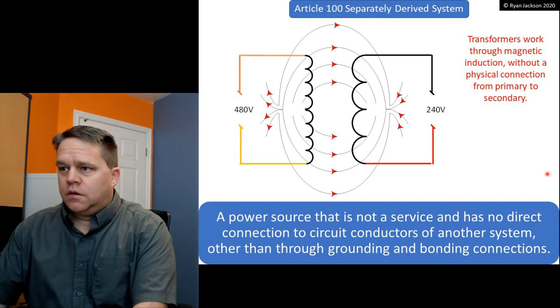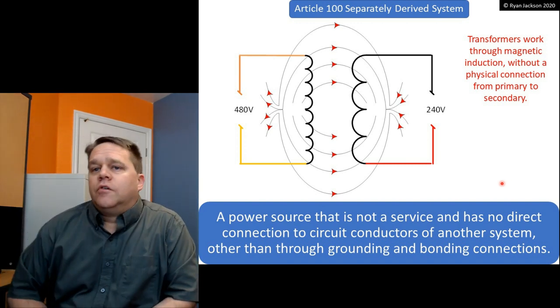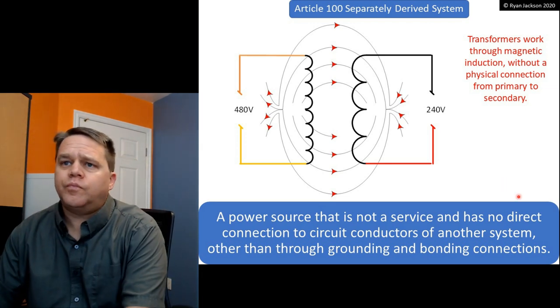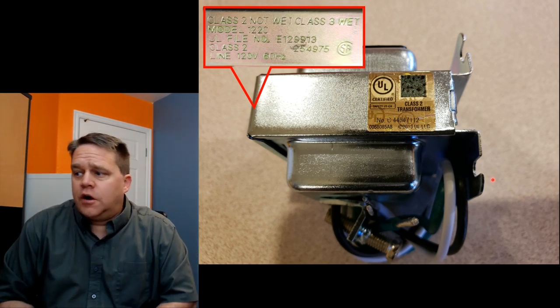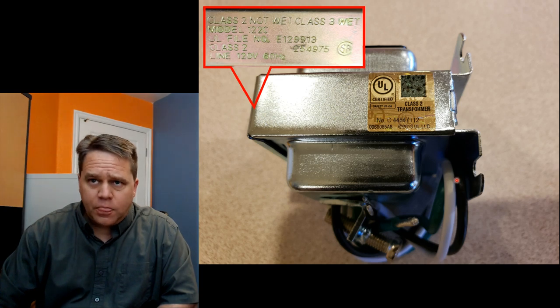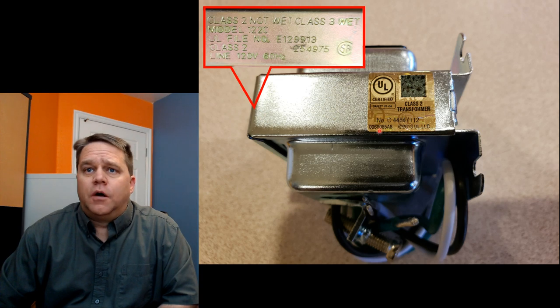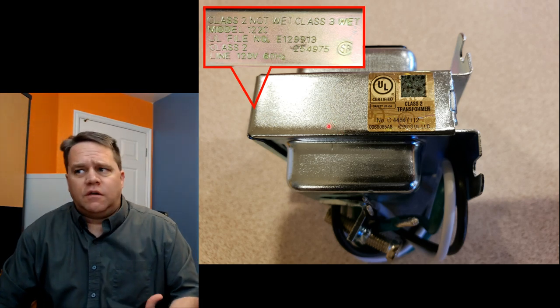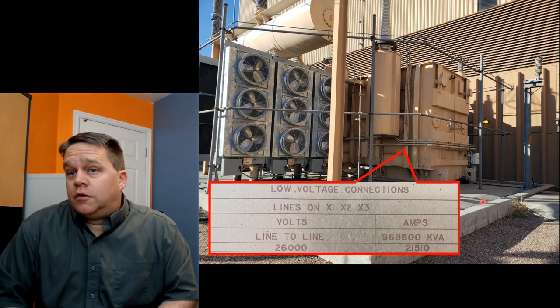So again, it's a power source that's not a service — not a utility — and it has no direct connection to circuit conductors of another system, done through mutual induction. That concept holds true whether we're talking about a tiny doorbell transformer — which in the NEC we call a Class 2 or Class 3 transformer, about 100 watts — or a large transformer. 120 volts in and the output is whatever we choose: 12 volts, 24 volts, up to 30 volts. Same concept.